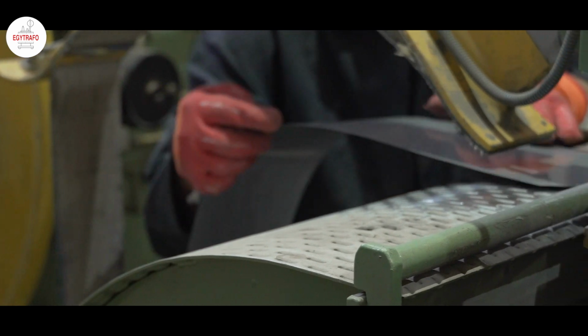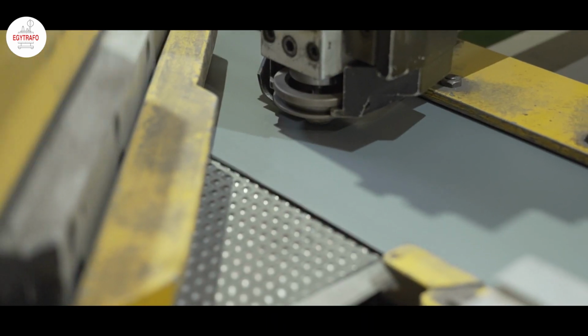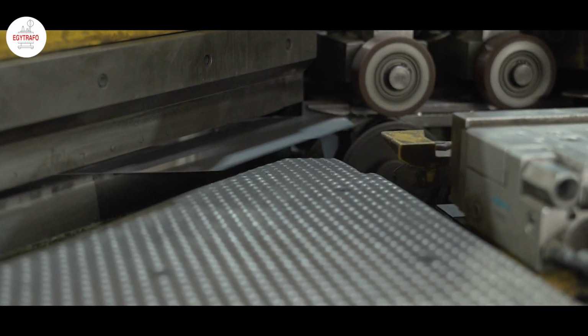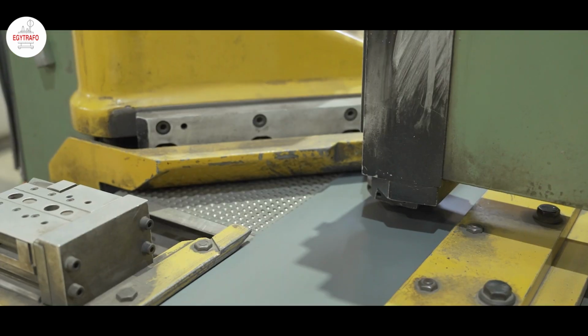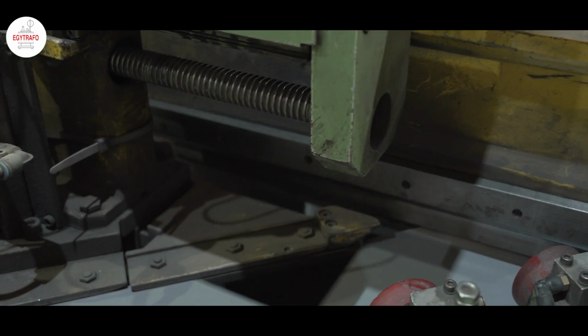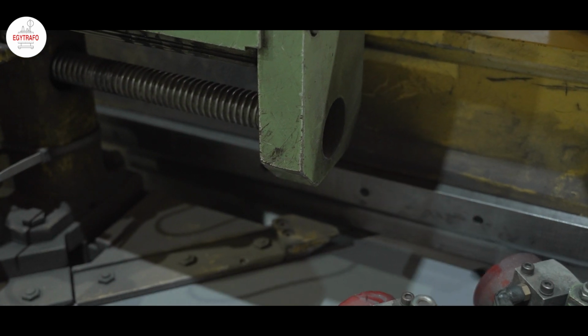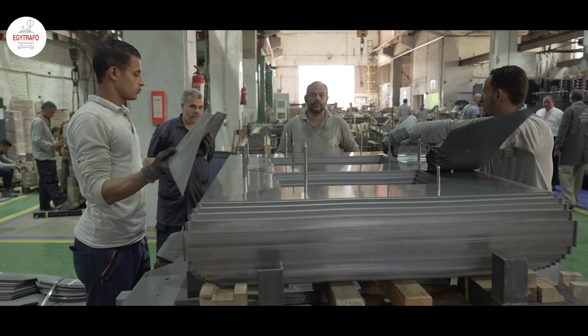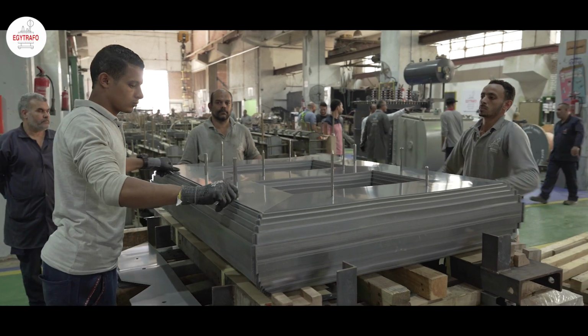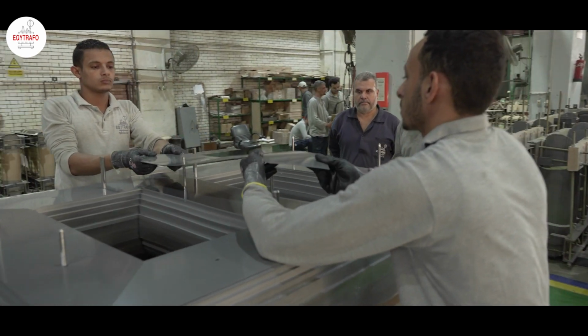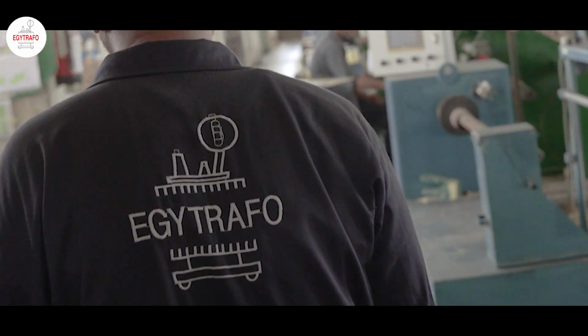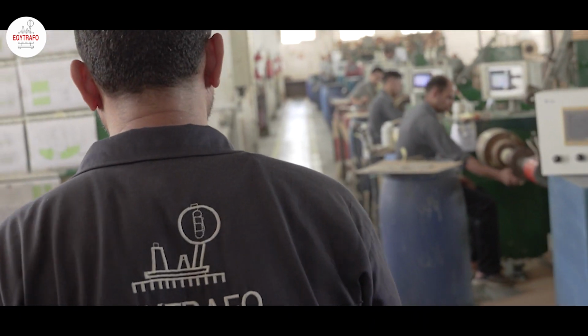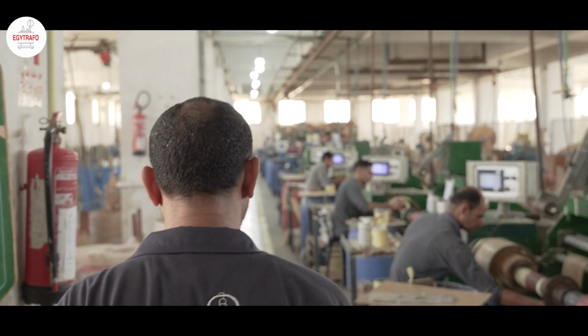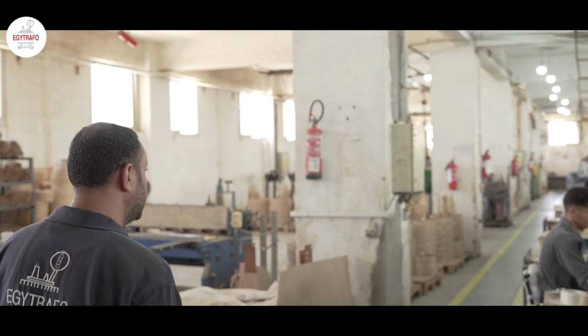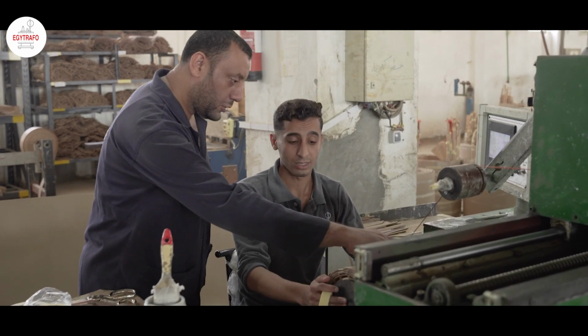Core design is an important factor of any transformer's efficiency. This results in high dimensional accuracy, excellent space factor, and low loss values. By using step-lap technology, the no-load currents can be reduced, improving the drawbacks associated with reactive power compensation. Windings. The windings are made of two components, conductor material and the insulation material. The conductors used are a high-grade electrolytic copper or aluminum.